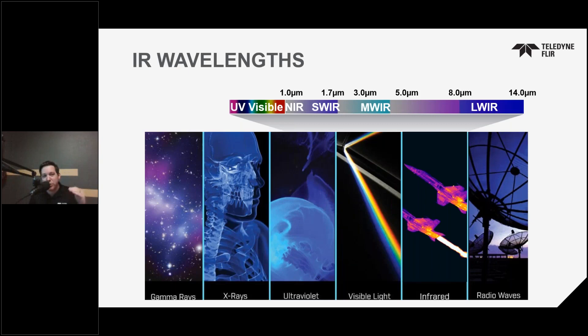That's why the true thermal bands start at around 3 micron, where you can begin measuring at about negative 20°C. Mid-wave infrared is the standard range for most radiometry and high-performance thermography applications. These detectors are exceptionally sensitive at typically better than 20 millikelvin NEDT. There's enough energy to adequately fill the detector wells and run at frame rates of one kilohertz or greater at full frame. This is really the workhorse waveband for cryo-cooled detectors.